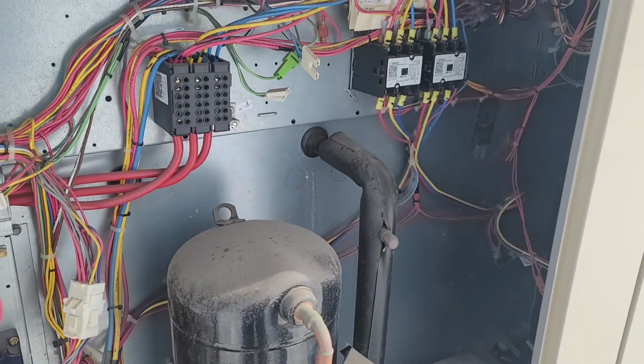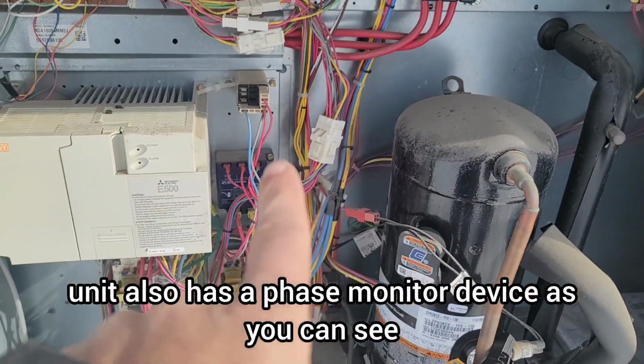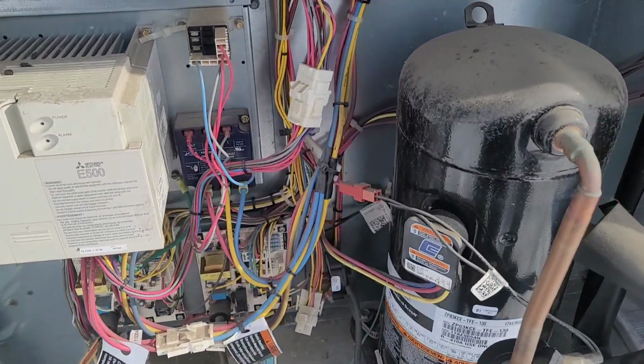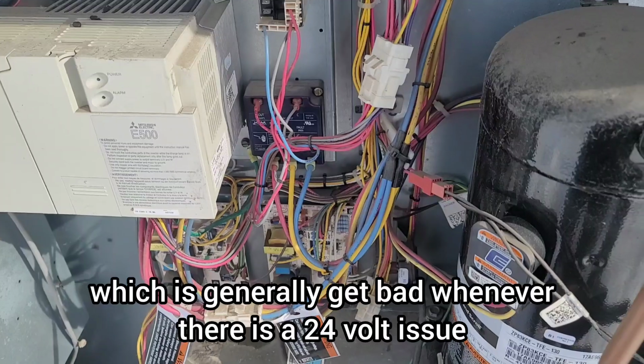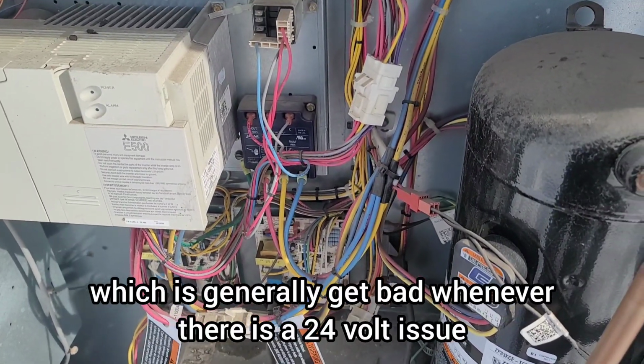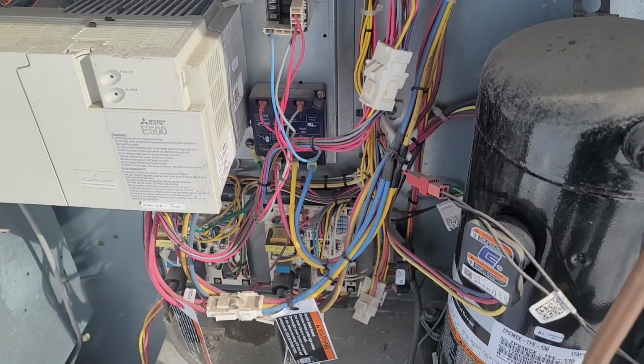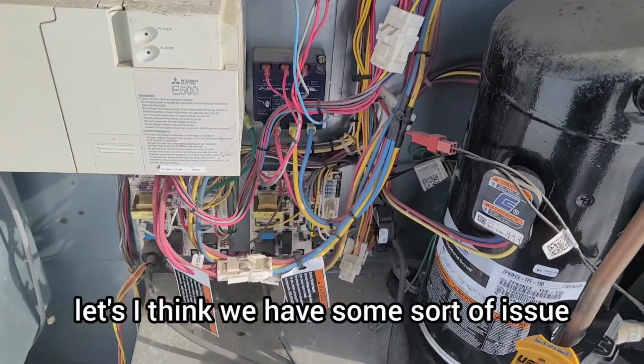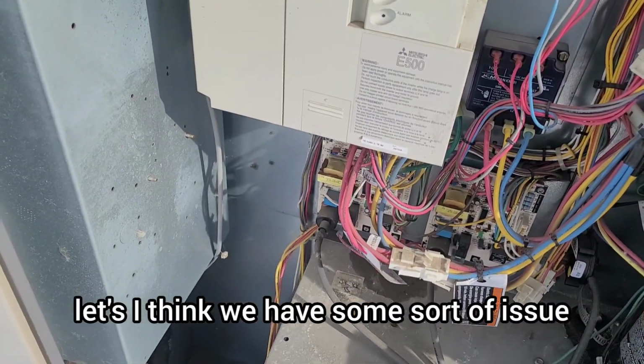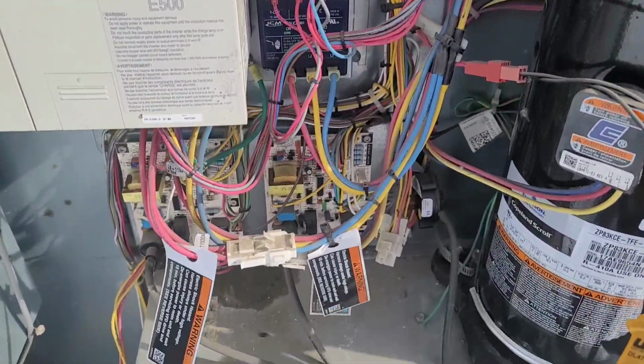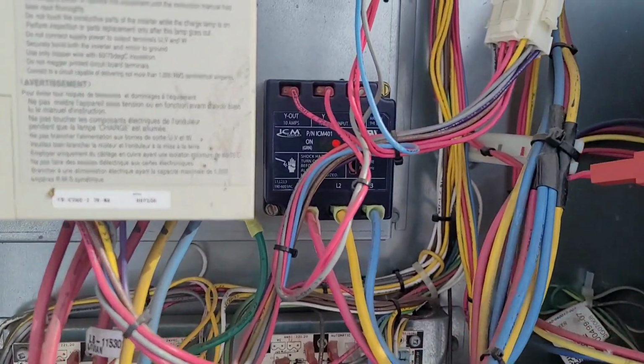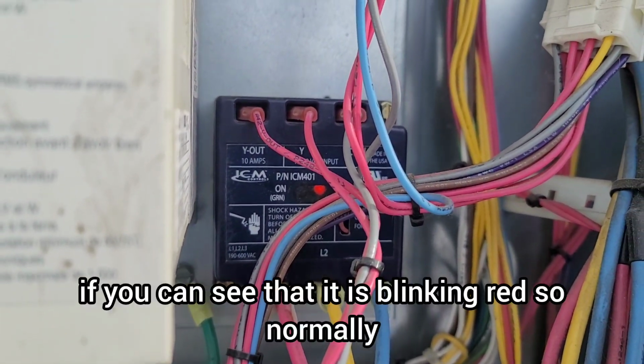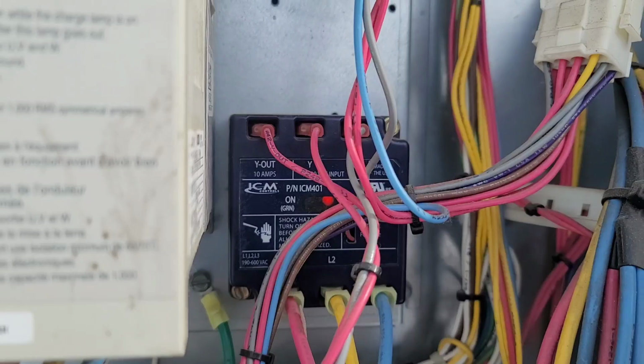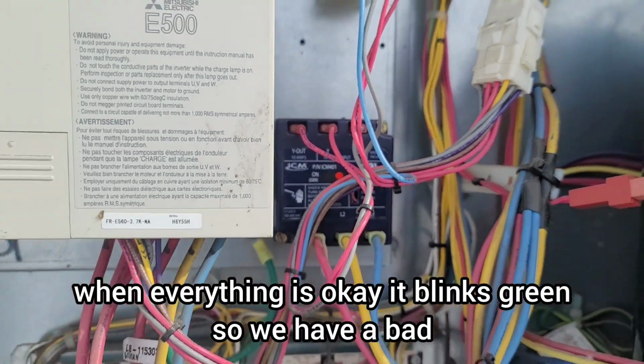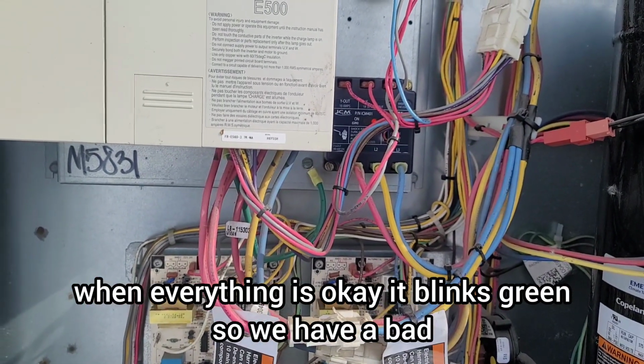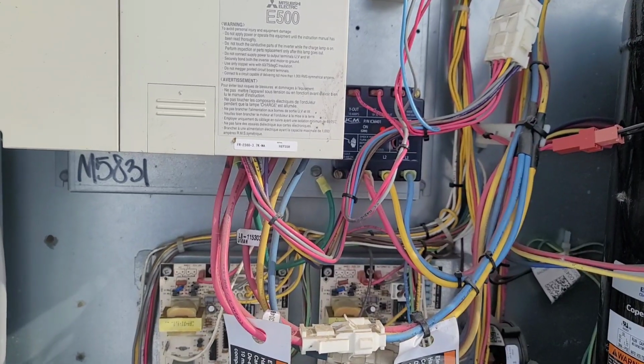And this unit also has a phase monitor device, as you can see, which generally goes bad whenever there is a 24 volt issue, when the unit is completely dead. So I think we have some sort of issue with the phase monitor. Okay, if you can see, it is blinking red. So normally when everything is okay, it blinks green. So we have a bad phase monitor.